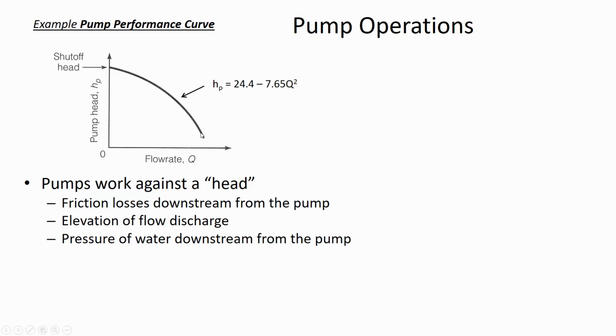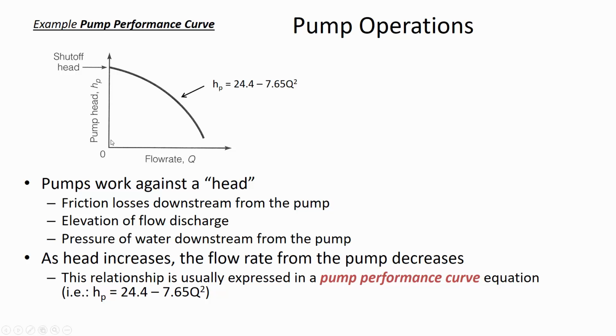But now if I made the pipe longer that the pump is connected to, that's going to increase the amount of friction that I have to overcome with the pump. And so if you're expecting it to do more work, then the flow rate's going to be decreasing. And oftentimes you can come up with an equation that describes the shape of that line. Here's just an example equation. Often they'd be provided by a manufacturer. They'd either give you an actual printout of the pump performance curve, or an empirical estimation of how the pump behaves at a range of flow rates, which pump heads it can achieve. So the main thing you need to keep in mind is that the pump performance curve has a decrease in pump head as the flow rate increases.